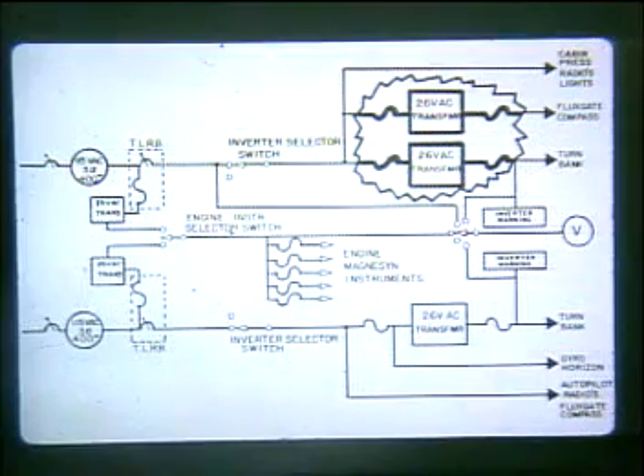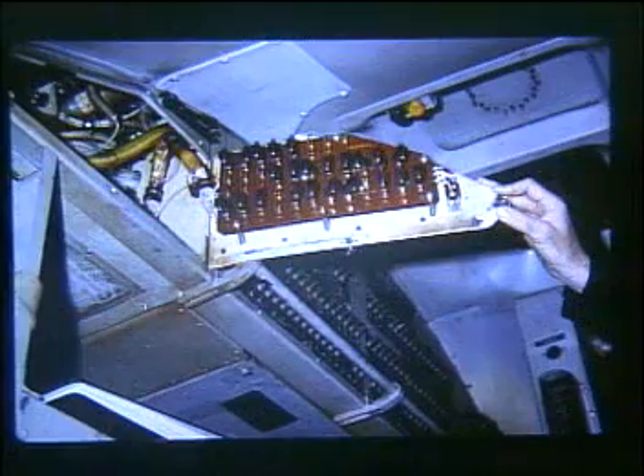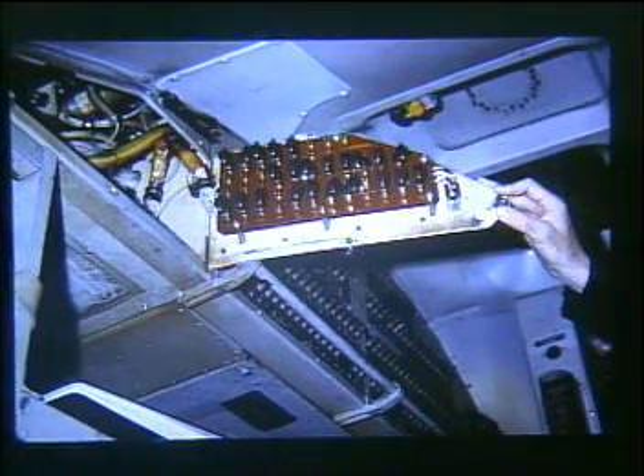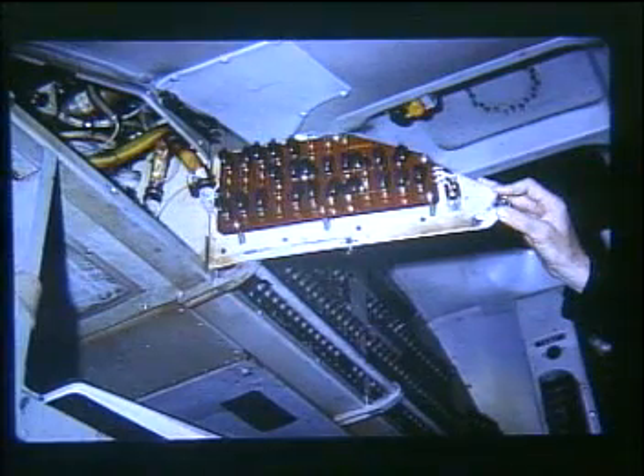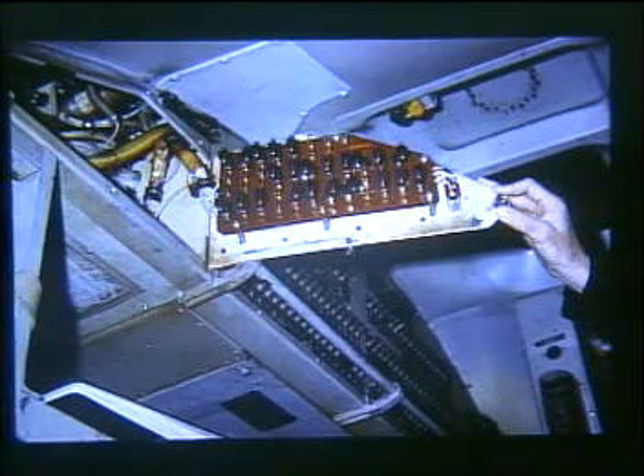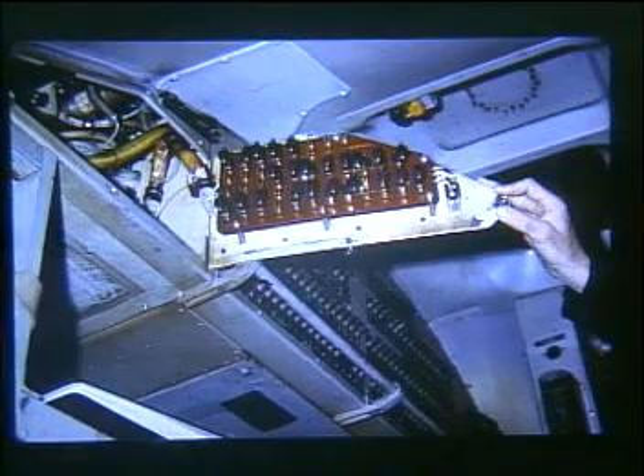The transformers are 3-phase input and output and are each protected by a pair of fuses called Captain's Flight Instrument Transformer fuses. The output of the transformers are fused in a comparable manner to protect the flight instruments. These fuses are referred to as the Captain's Flight Instrument fuses. The captain's flight instrument transformer fuses and flight instrument fuses are located in the AC fuse panel on the left side of the main circuit breaker panel. When facing the panel, the fuses are labeled and their functions listed on a placard on the outside of the door. The fuses are mounted in rubber blocks with a spare fuse.